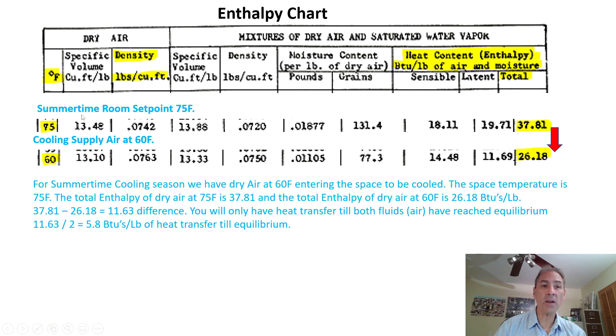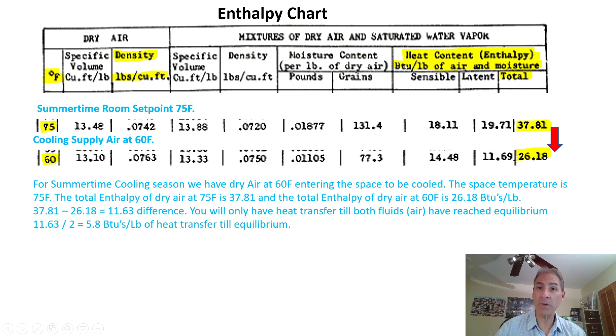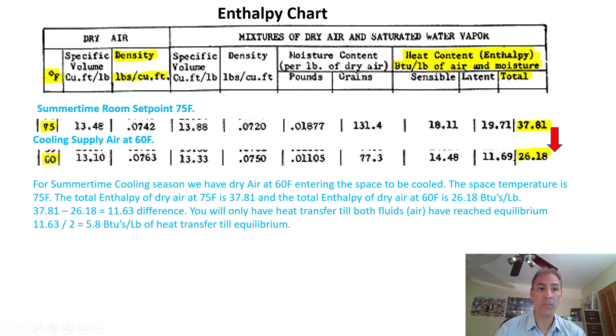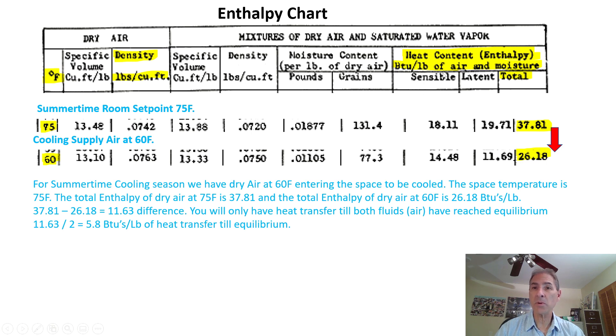In the summertime, the room set point on our thermostat is approximately 75 degrees Fahrenheit. I broke this section of the table out at 75 degrees Fahrenheit — this column over here is BTUs per pound of air. There are 37.81 BTUs in one pound of air at 75 degrees Fahrenheit, which is your room temperature. The supply air from your HVAC system is approximately 60 degrees Fahrenheit, and at 60 degrees Fahrenheit you're going to have 26.18 BTUs per pound of air.